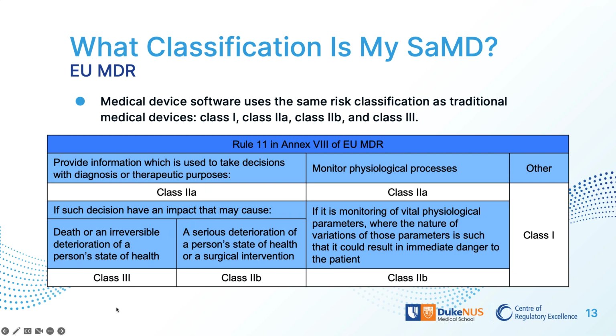If such a decision has an impact that may cause death or an irreversible deterioration, it would be classified as Class 3. And if it may cause serious deterioration of a person's state of health or surgical intervention, it would be classified as Class 2B. And a device intended to monitor physiological processes is classified as Class 2A, except if it is intended for monitoring vital physiological parameters, where the nature of variation of those parameters is such that it could result in immediate danger to the patient, in which case it is classified as Class 2B, and all other software is classified as Class 1.